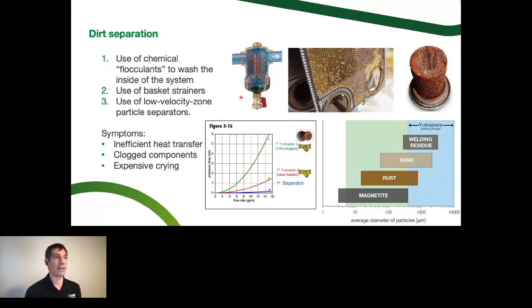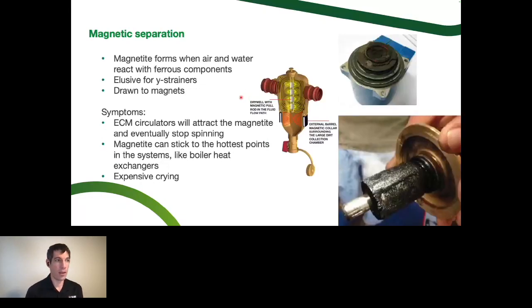Okay, the last piece is magnetic separation. This is a newer thing. In older buildings, and I think in the GTA there are going to be a lot of old buildings that maybe had cast iron boilers a long time ago, 100-year-old buildings, there's a lot of steel piping, cast iron radiators or something like that. So you've got a lot of metallic magnetic debris blowing around in that system. And an old cast iron boiler with a permanent pump wasn't really a big deal. It just kind of churned through, or it would settle to the bottom of the boiler heat exchanger, but they were big cast iron sections and it wasn't a big deal.